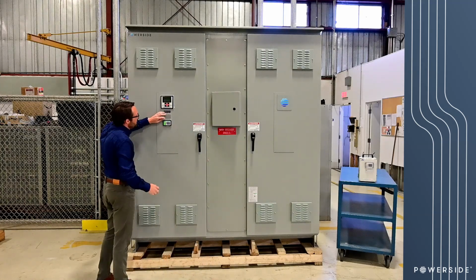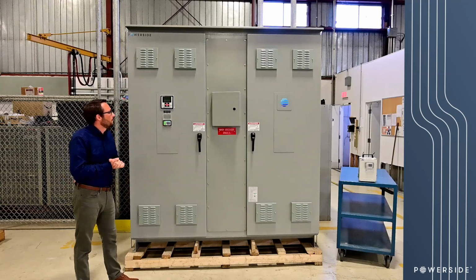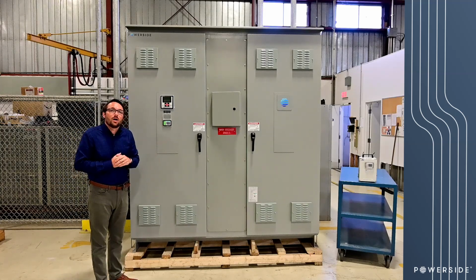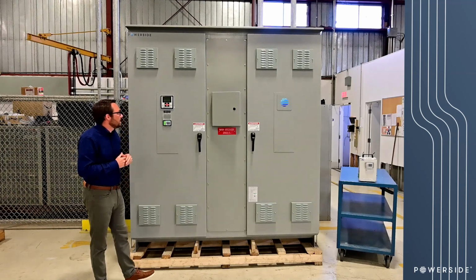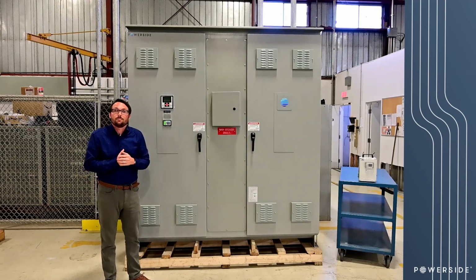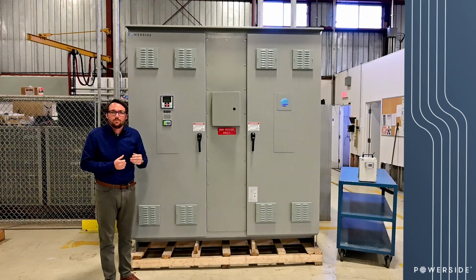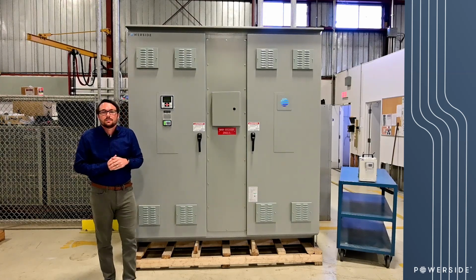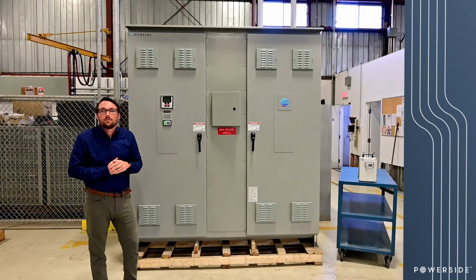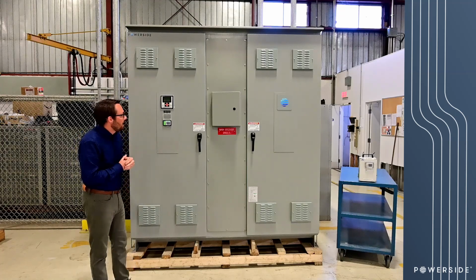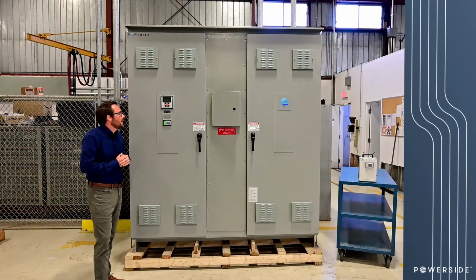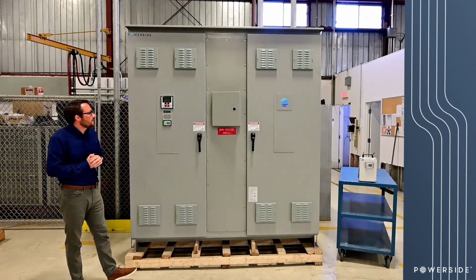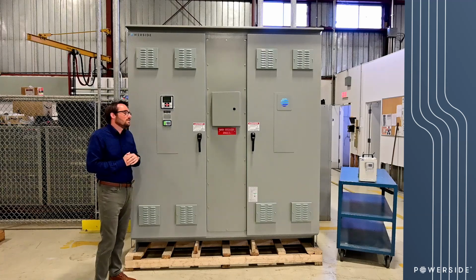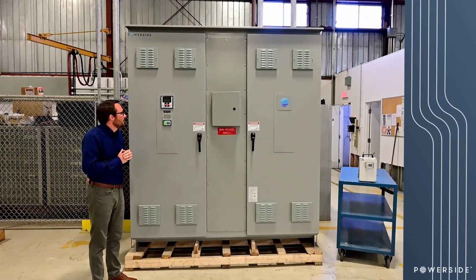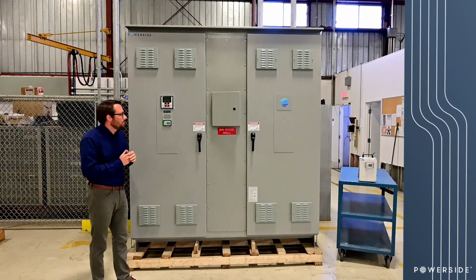So here we have a PQube which will be looking at and monitoring the main service on all 5 of the main transformers feeding the facility, which then they can look at and get accurate power data, compare it with their utility bills, as well as understand whether or not they're meeting their power factor requirements. One of the things that's really cool about the PQube is that it's got different inputs and outputs on it, and this is coupled with a digital input. We call it a wet digital input.